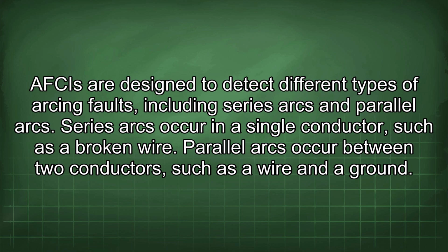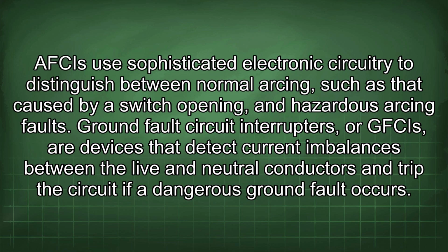Series arcs occur in a single conductor, such as a broken wire. Parallel arcs occur between two conductors, such as a wire and a ground. AFCIs use sophisticated electronic circuitry to distinguish between normal arcing, such as that caused by a switch opening, and hazardous arcing faults. Ground fault circuit interrupters, or GFCIs, are devices that detect current imbalances between the live and neutral conductors and trip the circuit if a dangerous ground fault occurs.